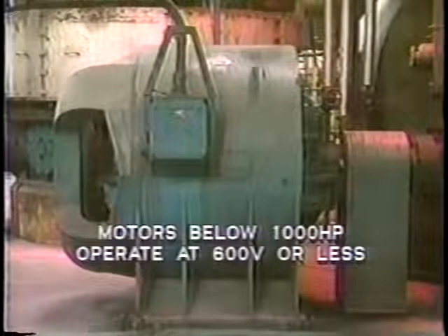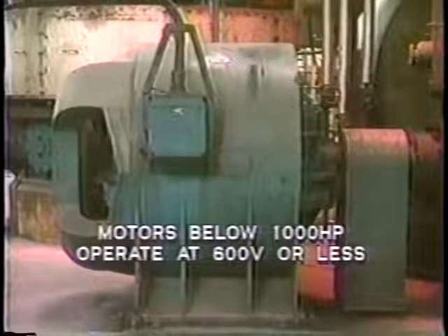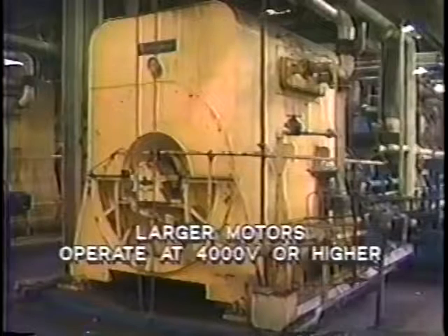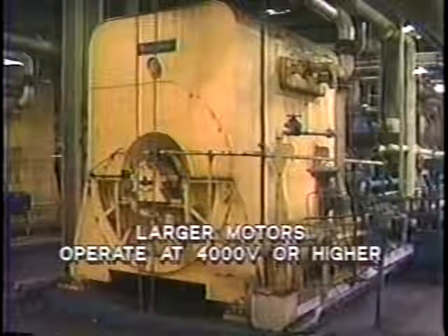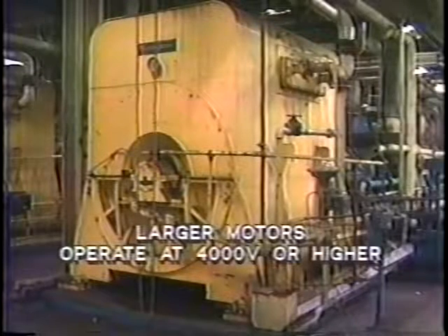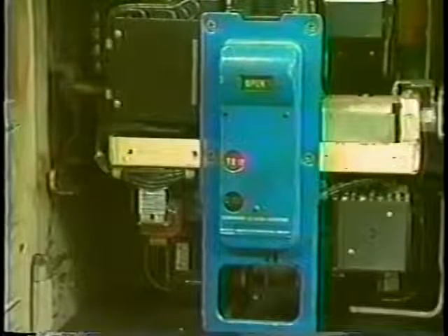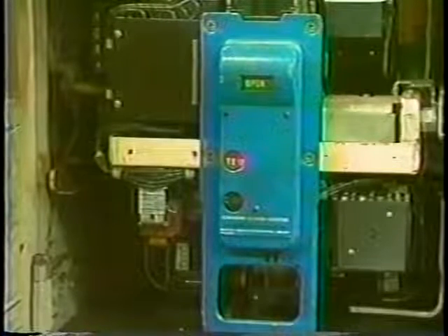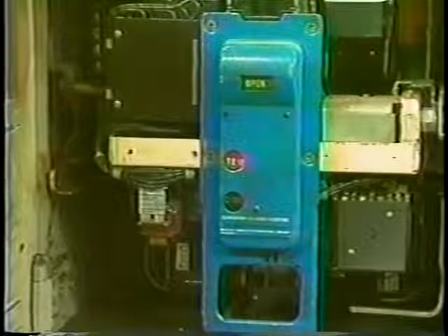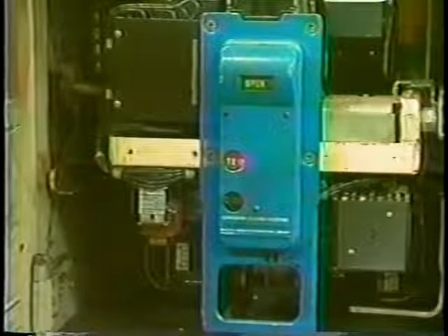The type of protection installed depends very much upon the size of the motor and its operating voltage. Generally speaking, motors up to about 1,000 horsepower operate at 600 volts or less, while larger motors commonly operate at 4,000 volts or higher. Small motors are generally energized through a contactor switch, which provides some built-in protection.